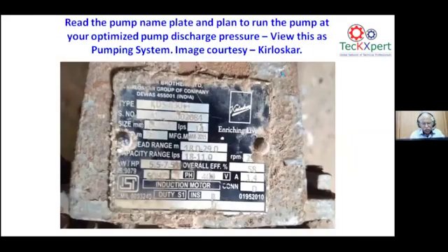That is on the compressor side. Let us just have a few slides on each and every utility where the scope for saving by condition monitoring is there. It is a typical pump we are using, hundreds of pumps we are using in our utility industries, where we find what is the optimized discharge pressure which you are supposed to have for the process.